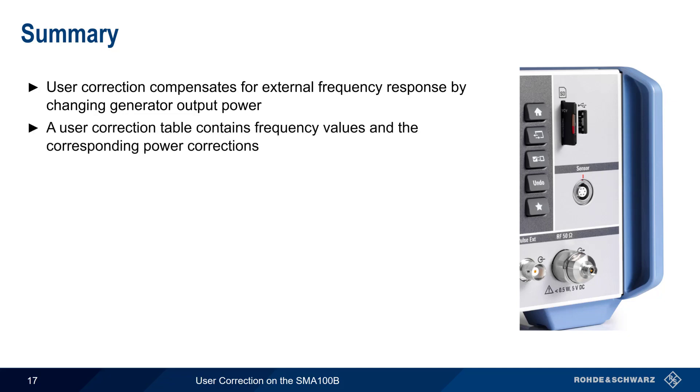Let's summarize what we've learned. User correction is a way that we can compensate for external frequency response, such as losses caused by cables, connectors, etc., by changing the output power based on the current generator frequency. This compensation is done using a user correction table, containing frequency values and the corresponding power corrections or offsets.